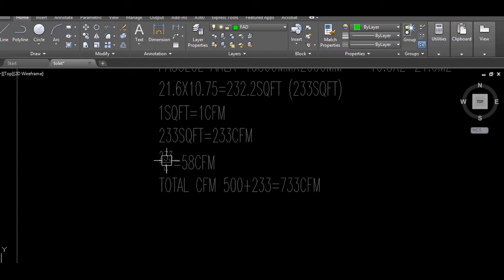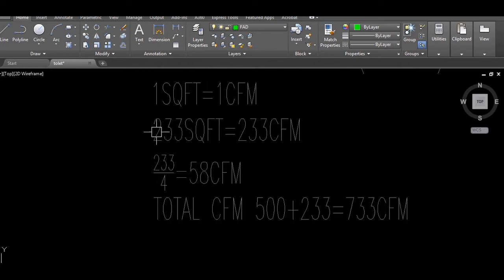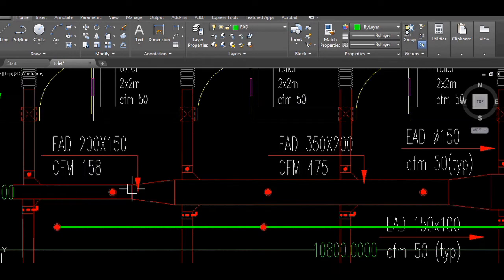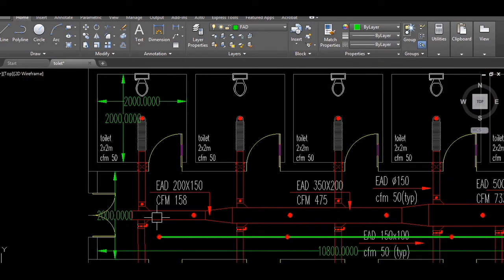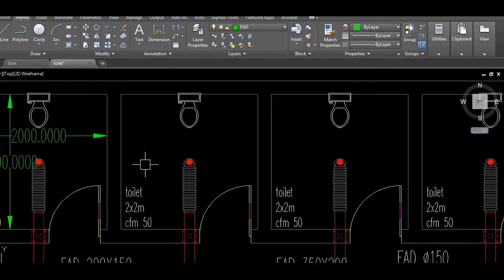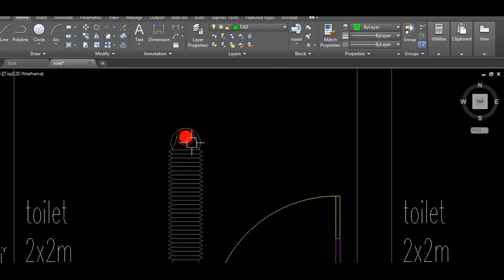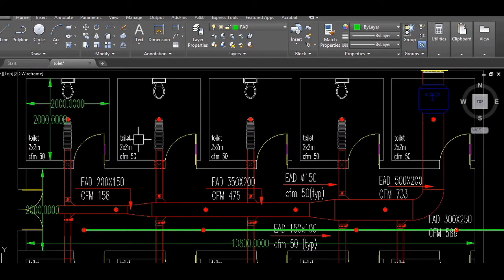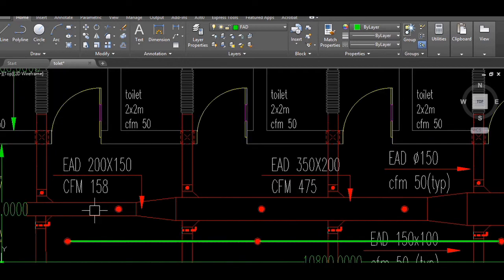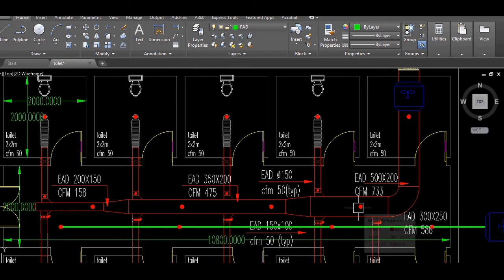The 233 CFM from the passage area is divided among four disc valves in the passage. Disc valves are terminal devices used to extract air. In the passage area I am using four disc valves. From each toilet, we are also using one disc valve each, with a capacity of 50 CFM per toilet.